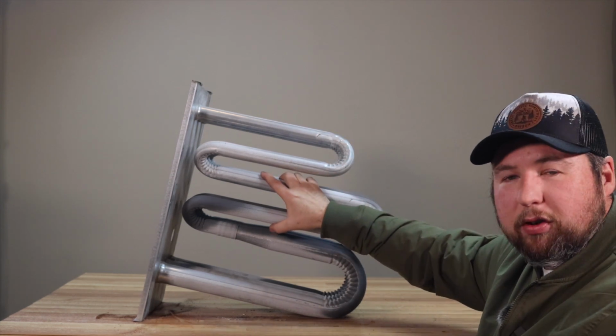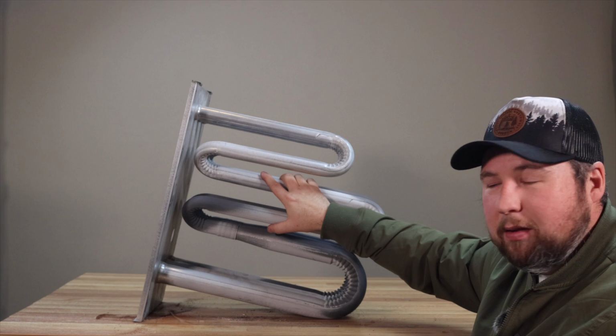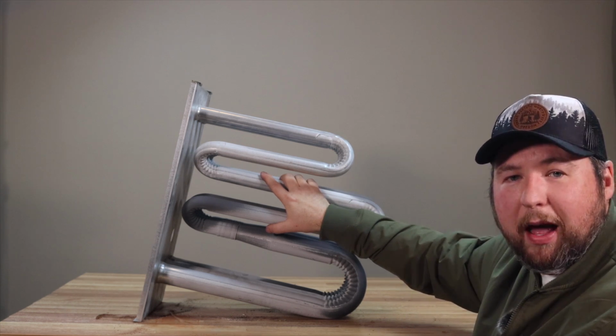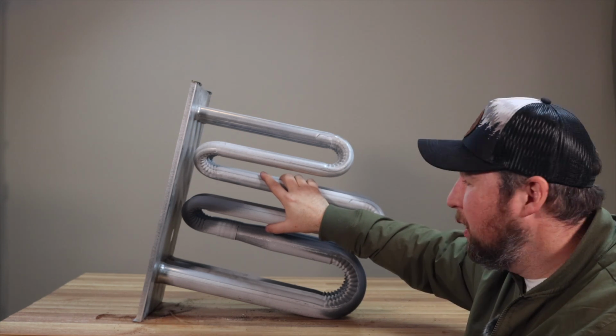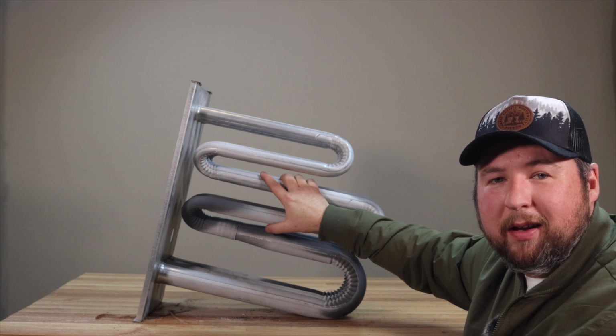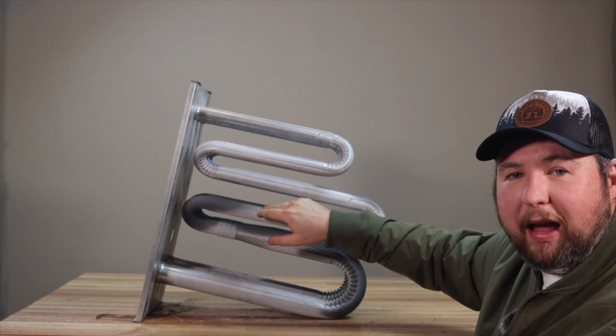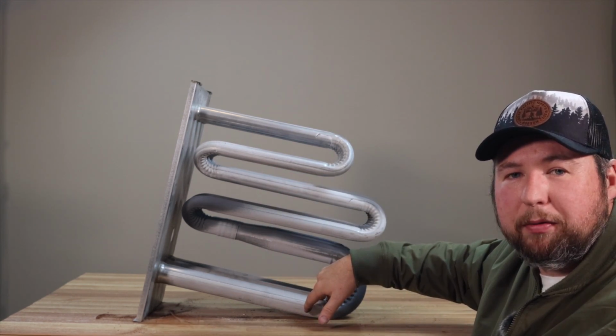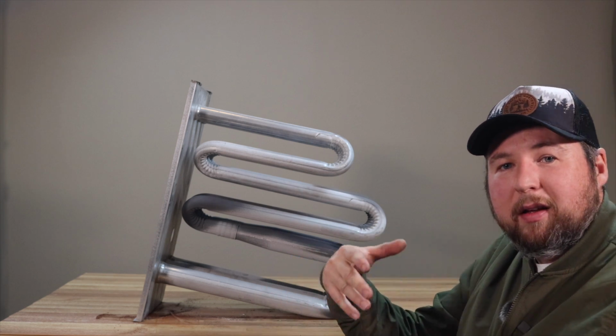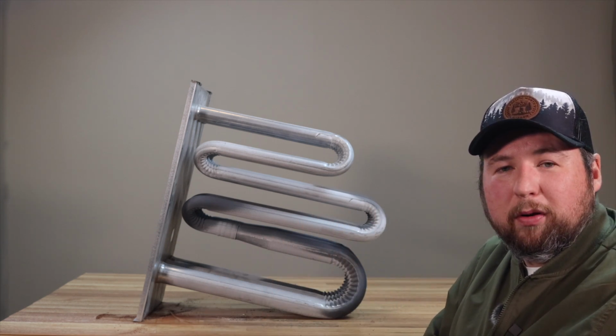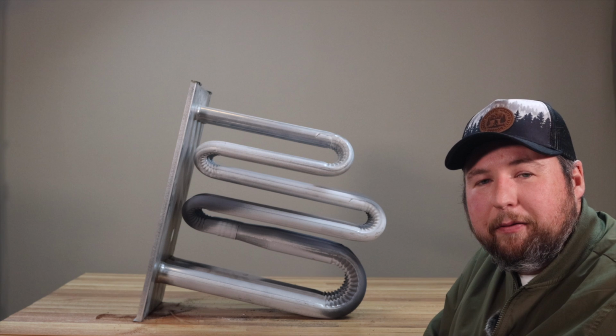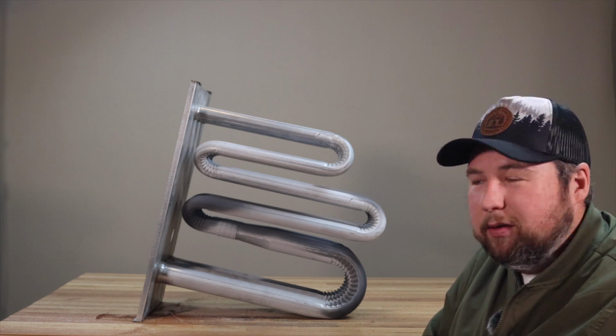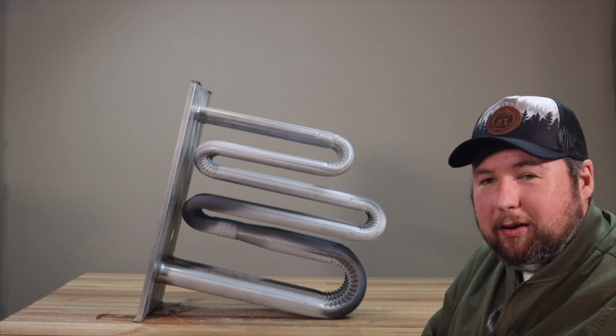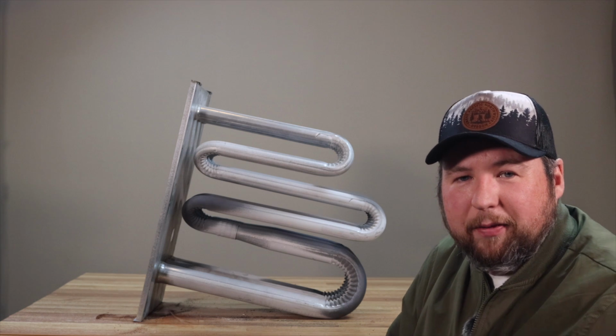One of the major issues that causes these to fail is overfiring. That means your gas pressure isn't set properly, so they just burn too hot. These are designed to have a lot of heat moving through them, but it's spread out. Over a course of time, all that heat is going to cause it to fail, but it should take lots of years. You should at least get 10 years out of a heat exchanger.